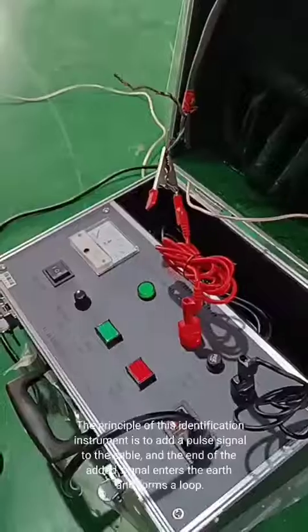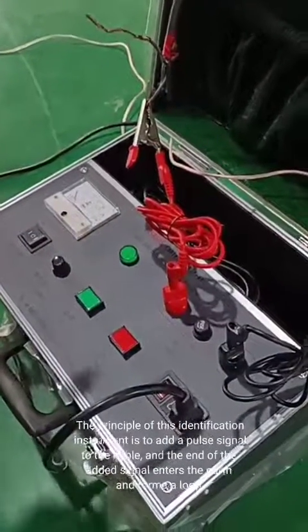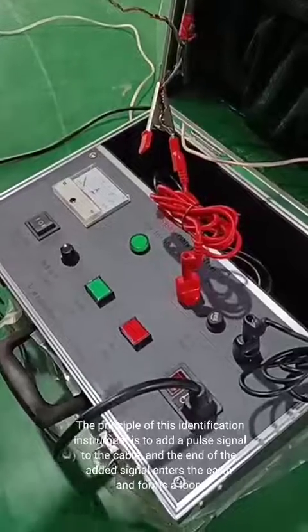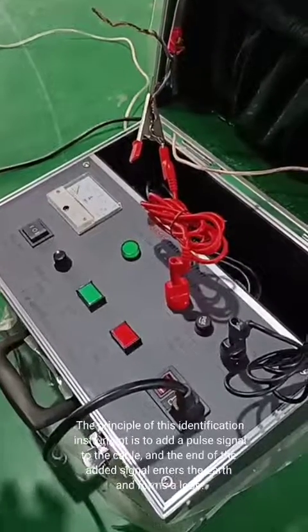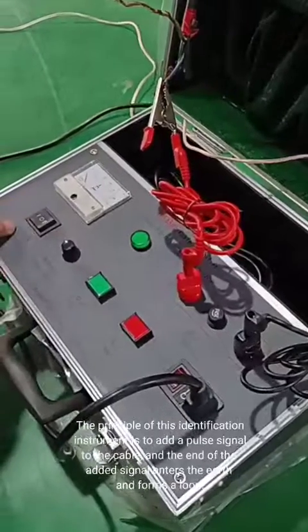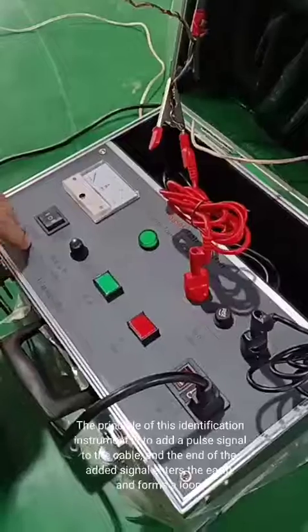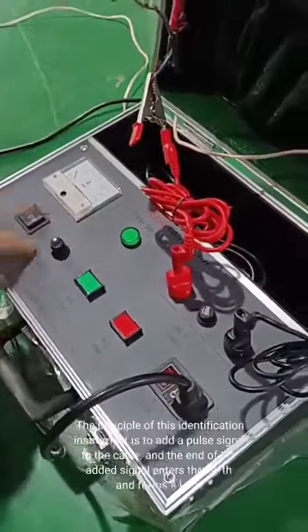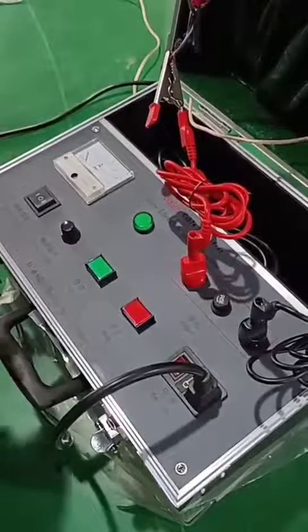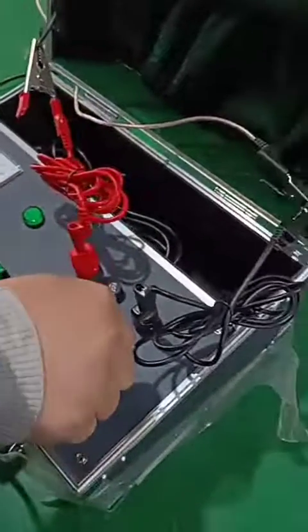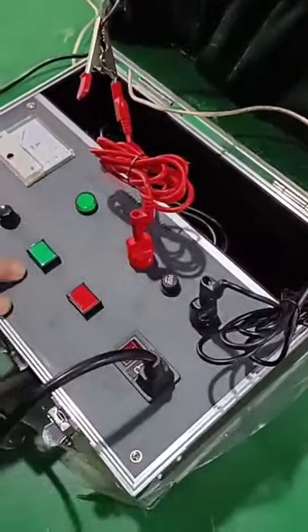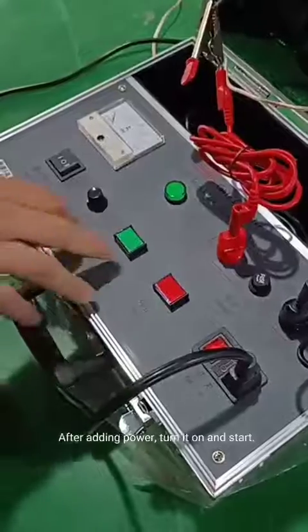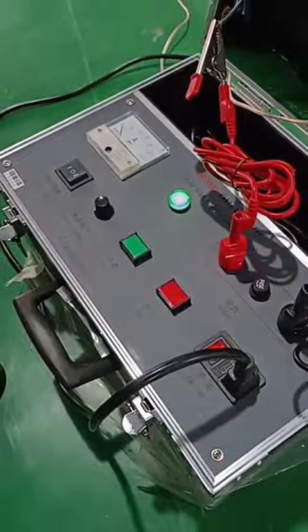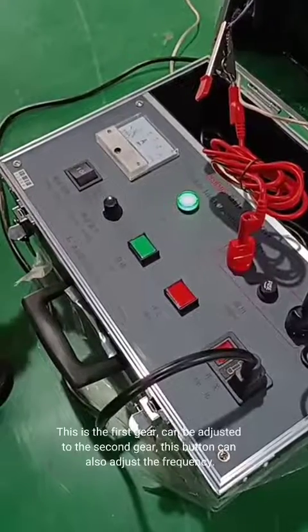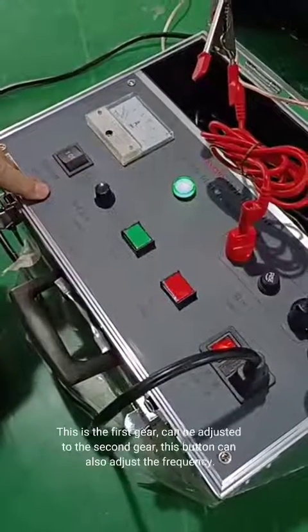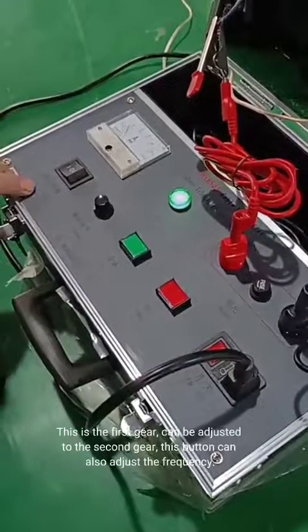The principle of this identification instrument is to add a pulse signal to the cable, and the end of the added signal enters the earth and forms a loop. After adding power, turn it on and start. This is the first gear, can be adjusted to the second gear. This button can also adjust the frequency.